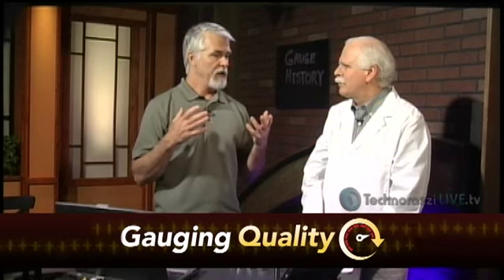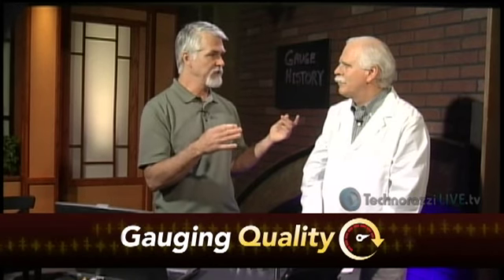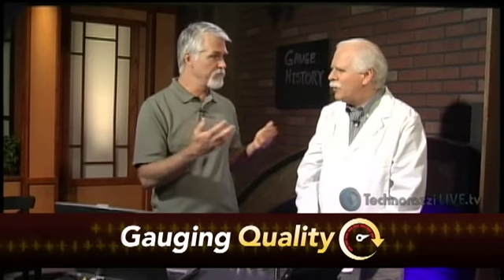So again, this would be one of those cases where a gauge would come in, it might calibrate just fine, and you could bring it back in, but maybe it took more calibration or more work than it did in the past. If you'd looked at the history, you would see that it wasn't following. And that's because gauges should typically, unless they're damaged, wear at a known rate. As long as they're used the same, and that's the key. You'd know something was different. Something has changed.